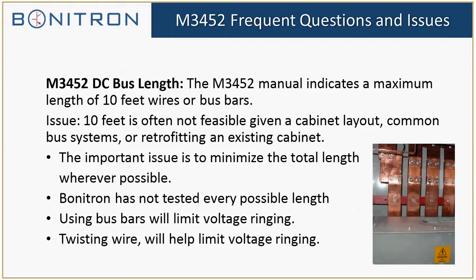We put this in there because our goal is to limit voltage ringing. Long DC buses have a bit of parasitic inductance, and as a result, when there's switching on and off, there can be small voltage spikes at the end, and it's just not good for equipment over time. And it's certainly not good for the M3452. While we don't have a hard limit where, at 51 feet, the unit will definitely destroy itself, we just can't test every situation. So we like customers to limit it to 10 feet.